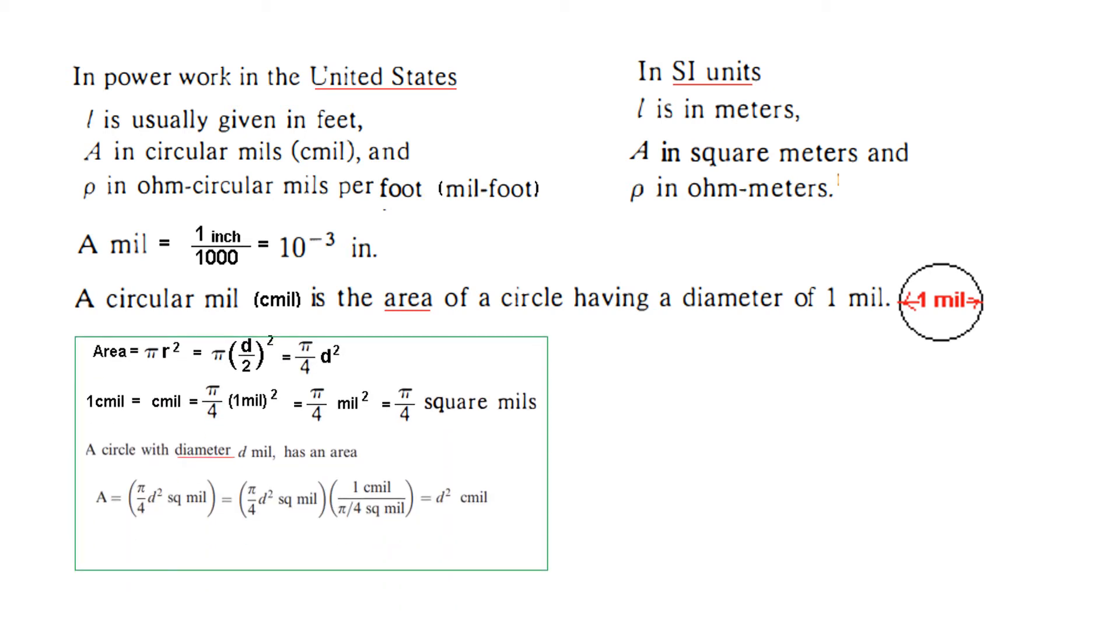I have explained here how the formulas have been derived. Area is πr^2, then r is d/2, so π/4 d^2. One circular mil equals π/4 mil^2. If the circle has a diameter of d mil, then the area in cmil is d^2 cmil. The crux is that we just keep in mind: if the diameter is d mil, then the area will be d^2 cmil. This is the only thing we have to remember.